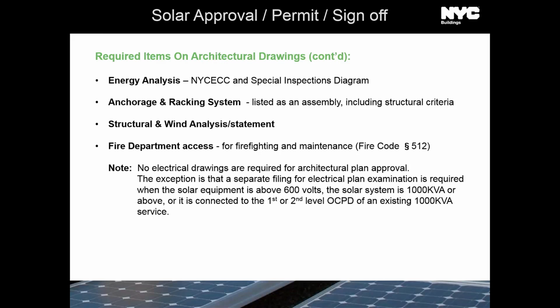You're going to have to do a separate filing if the electrical plan examination for the solar equipment is above 600 volts, the solar system is 1,000 kVA or above, or it is connected to the first or second level OCPD, I think that's overcurrent protective device, of an existing 1,000 kVA service.